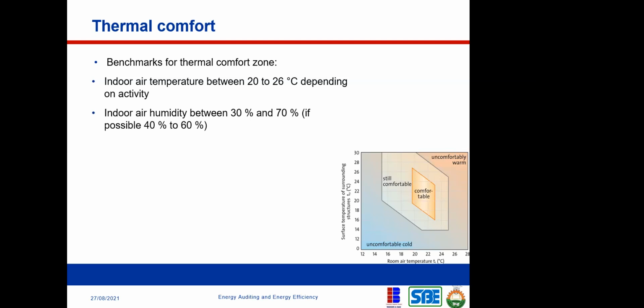So now let us talk about thermal comfort. Benchmark for thermal comfort zone. Now, indoor air temperature between 20 and 26 degrees centigrade, depending on activity, is fine. I told you 22, but here they're saying 20. Now, there are some people that are very active. They have a very high metabolic activity. Their body system has a very, very high metabolic activity rate. So for those kinds of people, maybe they might want to keep it at 20. But between 20 and 26, you're comfortable.